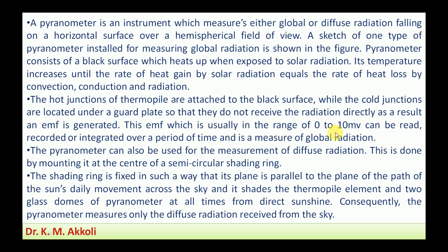The EMF, which is usually in the range of 0 to 10 millivolts, can be recorded and integrated over a period of time, and is a measure of global radiation. Whatever EMF we measure will be the record of global radiation, proportional to the radiation received. The pyranometer can also be used for measurement of diffuse radiation by mounting it at the center of a semicircular shading ring.